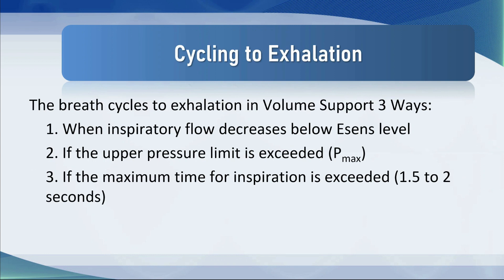Cycling to exhalation can occur three ways in volume support. First, when the inspiratory flow decreases below the expiratory sensitivity level — for example, if it's 25% of peak flow and the peak flow is 60 liters, it will cycle off at 15 liters. Second, if the upper pressure limit is exceeded — the Pmax — usually caused by the patient coughing or bucking on the ventilator. Third, if the maximum time for inspiration is exceeded, which defaults at 1.5 to 2 seconds — you certainly do not want to see two-second-plus inspiratory times on pressure support.